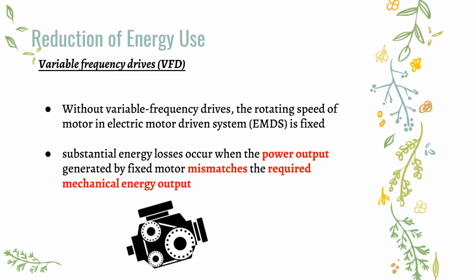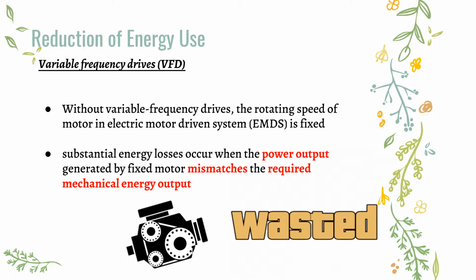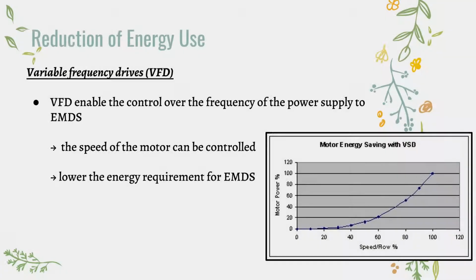There are numerous electric motor driving systems in existing buildings, for example in the cooling system. Substantial energy losses occur when the power output cannot match the energy requirements, because without VFD we cannot control the rotating speed of the motor. But with VFD, we can control the frequency of power supply, which means the speed of the motor can be controlled, lowering the energy requirement for EMDS and reducing the energy loss in the system.